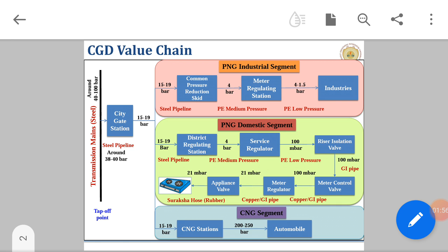goes to the meter regulator and it becomes 21 millibar. The gas which is coming to our house is at 21 millibar. It passes to the appliance valve and Suraksha hose rubber and then it comes to the stove where it is 21 millibar. In the CNG segment, the 15 to 19 bar CNG station gas is compressed and it goes to 250 to 200 bar, which goes to the automobile.